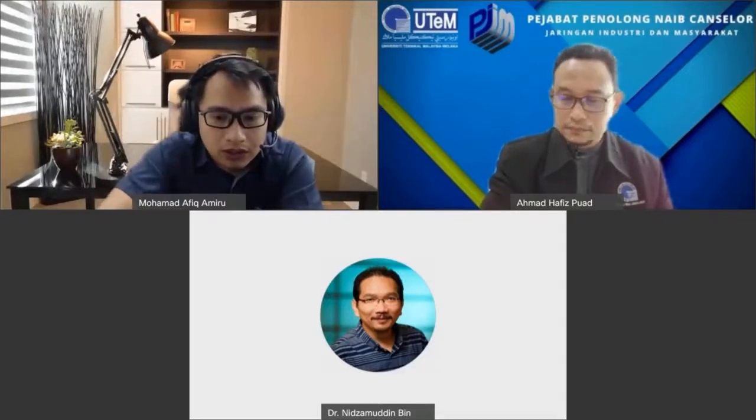This presentation comes from the experience of collaborating with one of the industrial sector companies in Kluang, a collaboration between UTeM and the company under a matching grant. We developed one machine, which we call a pressure safety valve or pressure relief valve test bench, which verifies or tests a PRV for calibration purposes.